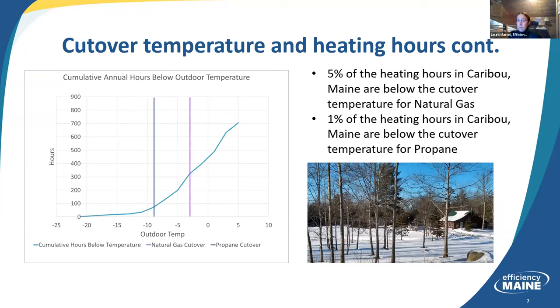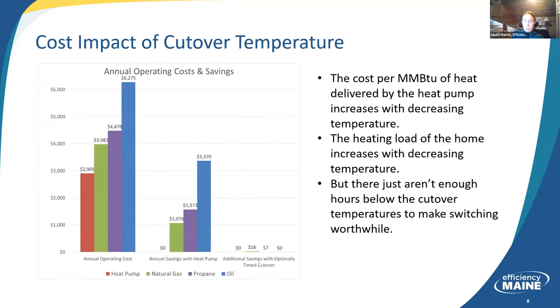And I would not recommend anybody sitting next to their thermostat trying to time switching between systems. And even if it's automated, it's just not worth it. And I'm going to try to convince you with this chart here. So the bars or the columns on the left chart are the annual operating costs for the various heating systems. So in red is the heat pump, in green is natural gas, a boiler, purple is propane, a boiler, and oil is the blue, also a boiler.